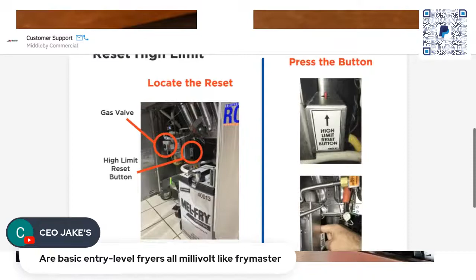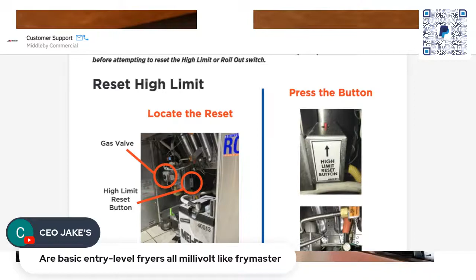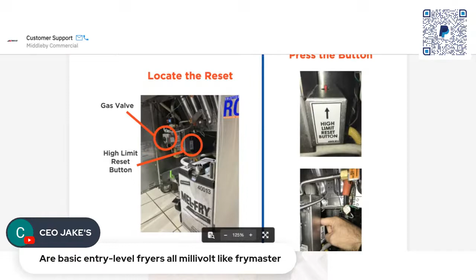Oh, good one, high limit. Here we go. So how to reset the high limit? It is just a simple push of the button, doesn't get any easier than this. Big orange button, big sign saying, hey, push here. Now, if you push that orange button and you hear a click, that means the high limit was tripped. If you push it and it's a little spongy, it might not have been tripped. And if you push it and it's not really responsive, it might actually have damage to it. This shows you in proximity where it is.